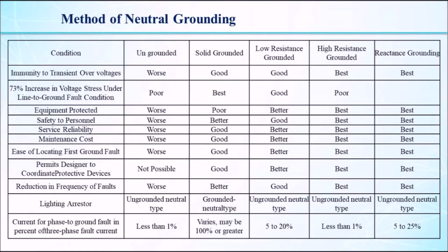An ungrounded system is complicated for locating faults. A second fault on another phase may occur before the first fault can be cleared. This can result in very high fault current which may damage equipment and cause disruption of both circuits. In a solidly grounded system, there is no service continuity on the faulty feeder. The danger to persons is high during a fault as the touch voltage created is high. If we have a closer look at resistance and reactance grounding, it gives better performance than ungrounded and solidly grounded systems by limiting the maximum fault current to a value which will not damage the equipment, and allowing sufficient flow of fault current to detect and operate the earth fault protection relay to clear the fault.